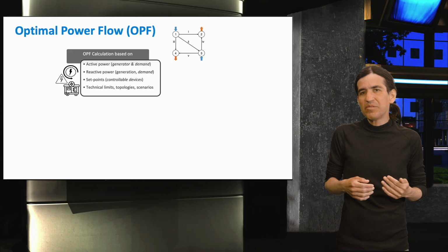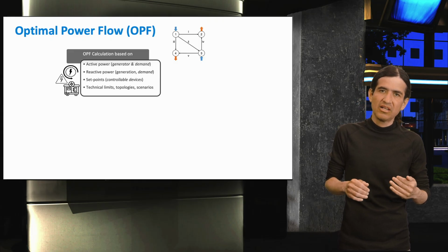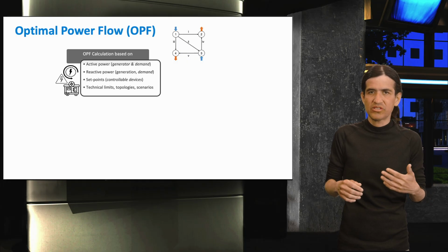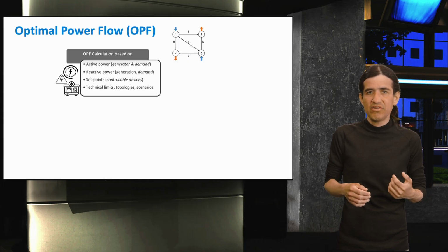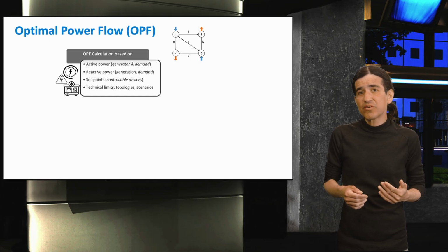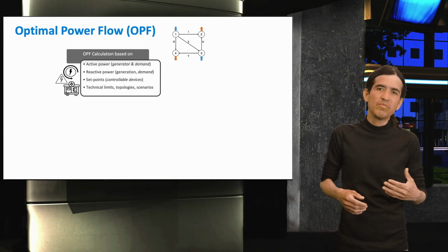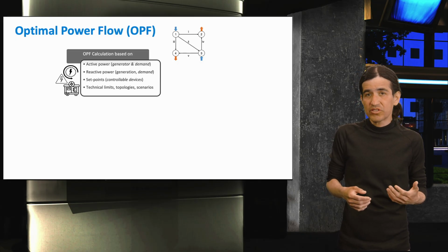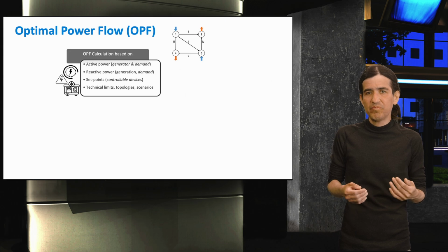The inputs of optimal power flow usually consist of network data like buses, lines, transformers, compensation, storage, etc. Generator limits and cost, load demands, profile, limits, cost, and system technical constraints. The ranges for adjusting the set points of controllable assets define the bounds of the control or optimization variables for the search of the optimal or near to optimal solution.